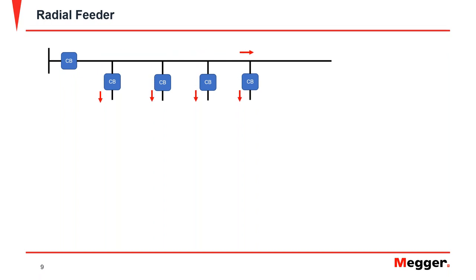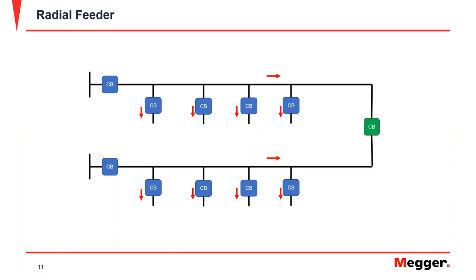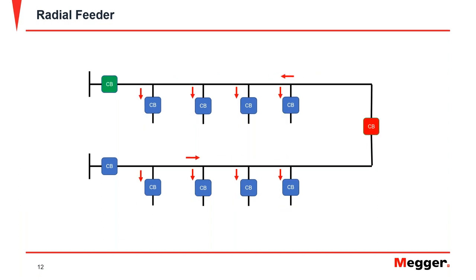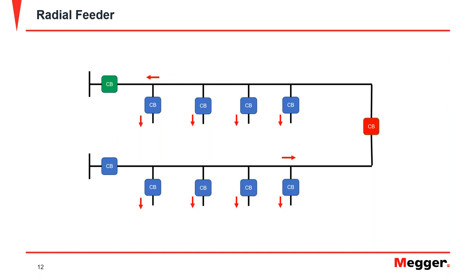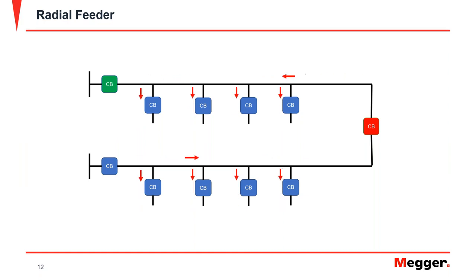A disadvantage of radial feeders is that when the main circuit breaker opens, all loads connected to the same feeder lose their power supply. One way to address this is connecting multiple feeders with normally open ties. If one feeder loses power, the tie can be closed to reconnect and provide power to customers on the second feeder. We will see these schemes in the distribution feeder automation discussion at the end.